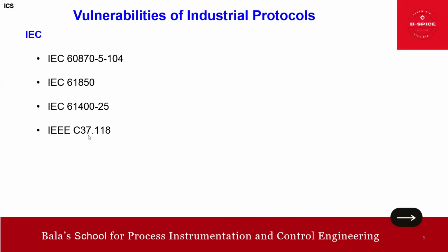Now we talk about IEEE C37.118. In substations, this protocol is commonly used to establish synchronization, and it defines standards for data transmission formats. It outlines four distinct message types: data, header, configuration, and command. In a typical transmission process, these messages are converted into frames. Just remember that C37.118 is used to establish synchronization.